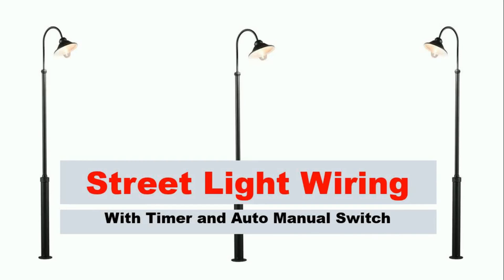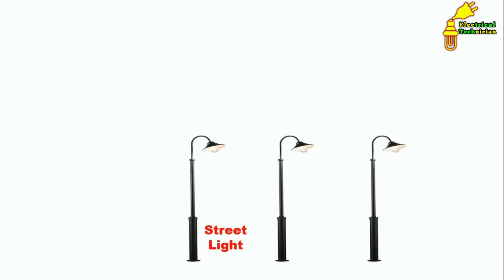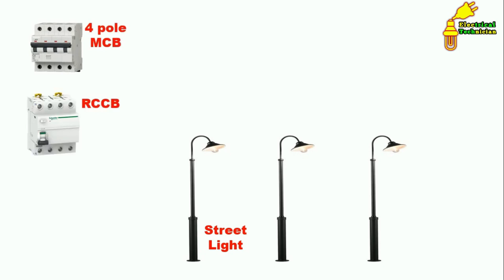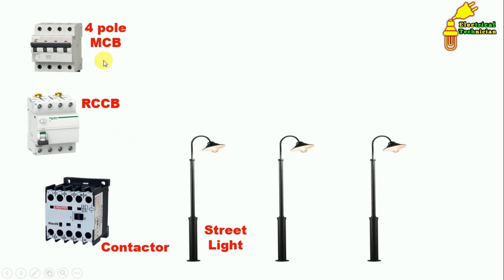Today we are going to learn how to do distribution of power supply for street lights. First of all, we use a four-pole MCB, and to protect from earth fault, an RCCB is also used. After this, to turn on and off, we are using a contactor. The MCB provides protection from overcurrent and short circuit, and the RCCB gives protection from earth fault.